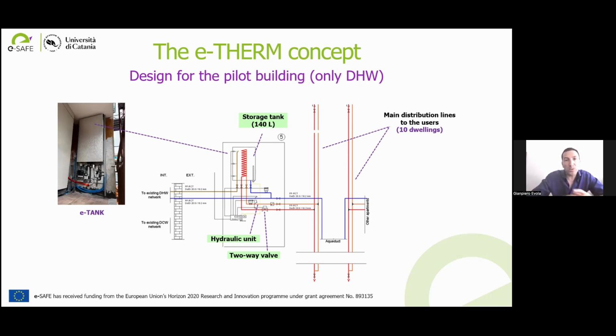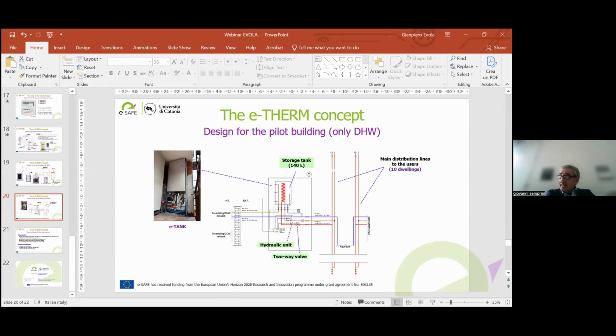So we are confident that once we optimize the sizing and the control logics, our system will have lower electric energy needs than traditional systems. Can I add something about this consumption? This centralized solution, I think, is very interesting, probably in North European countries, where there are very low temperatures during winter and they use a higher temperature in the pipe network. Using just one pipe network for both heating and charging domestic water can greatly reduce the thermal losses during the on-off period.